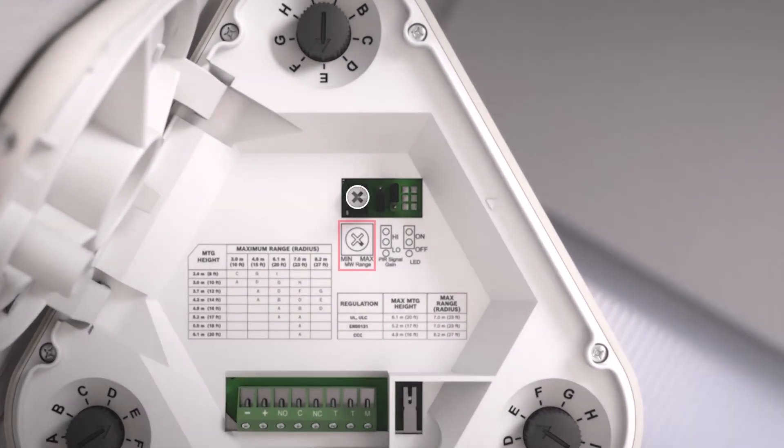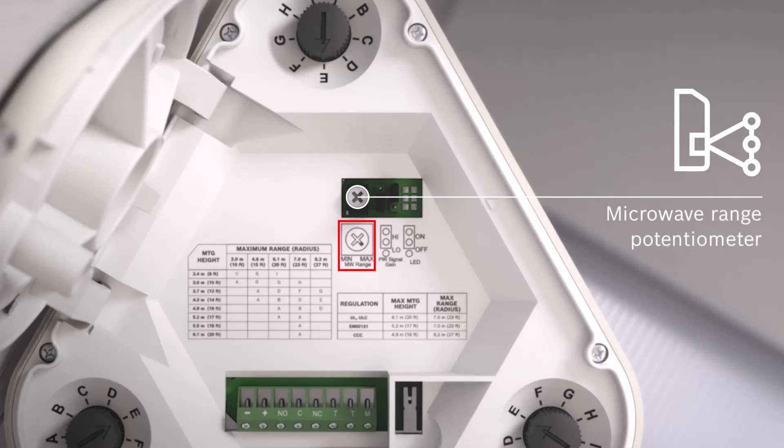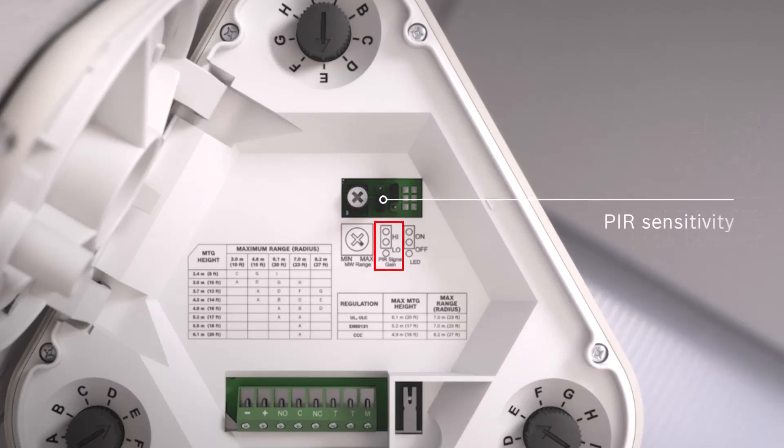For the Tritec series, the microwave range can be adjusted with a potentiometer. Turn clockwise to increase and counter-clockwise to decrease the microwave range. PIR sensitivity can be set to low or high. The tricolor LED may also be turned on or off.